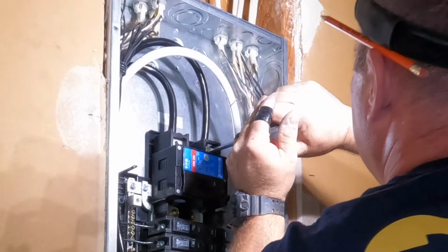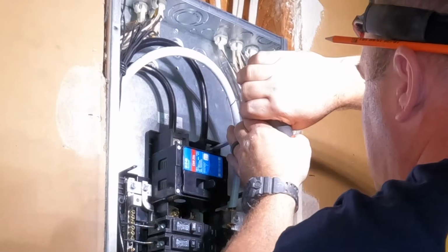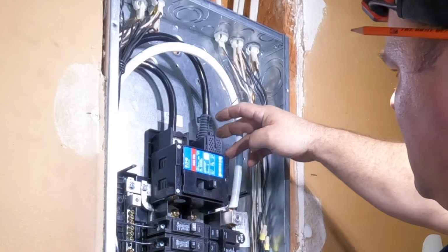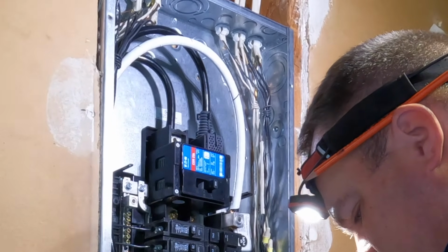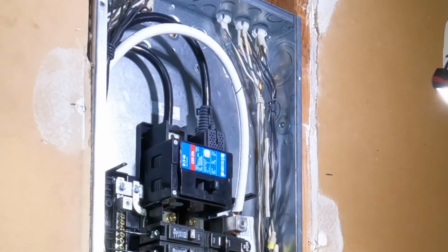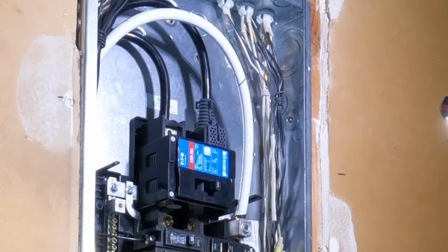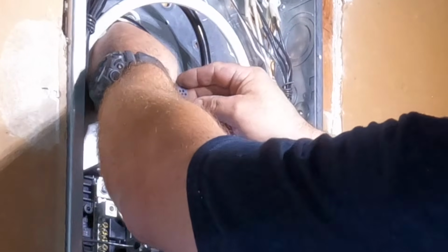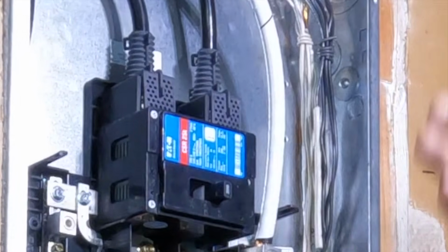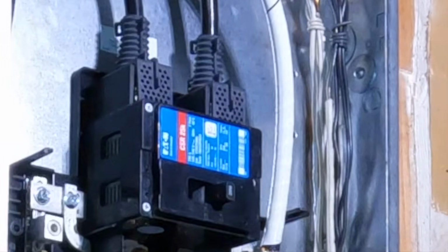So that's a 200 amp main breaker right there. And a few code cycles ago, we were required to put these guards over the live terminal. The idea is that there's less space for someone working inside that panel to get shocked. I mean, you've got an open bus bar down below there too. But I understand the intent of the code change, and I think it was a good one.